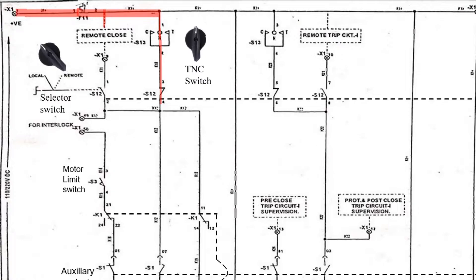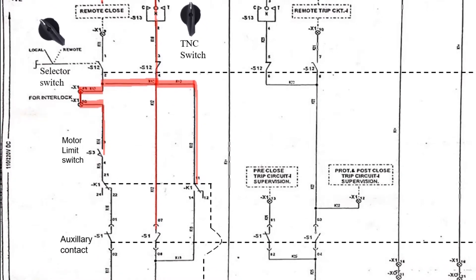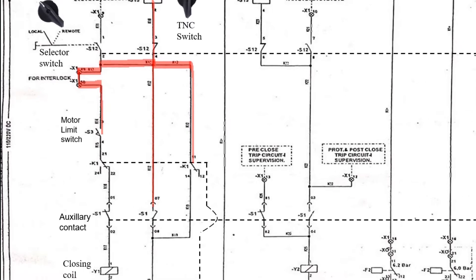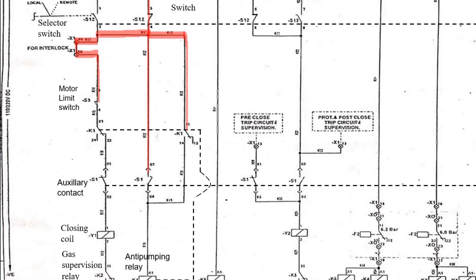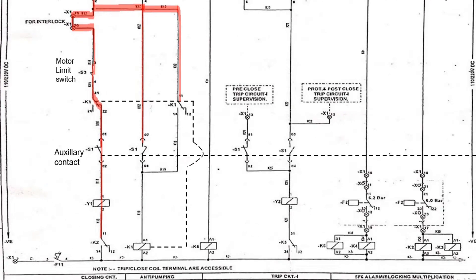Current will not flow through the right-hand side paths but will flow from the left side if the interlock is in okay condition. Now the current will stop if the spring is not charged. If the spring is charged, the motor limit switch will be in closed position and the current will flow downwards. It will flow through auxiliary contacts S1 and closing coil Y1, but will stop at K2, which is an SF6 gas supervision relay.